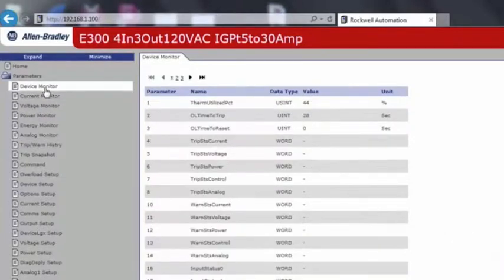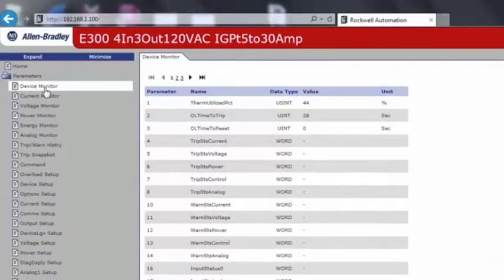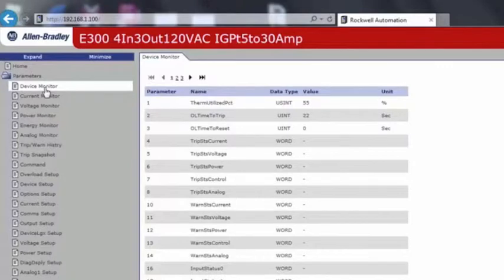On the device monitor screen, you can watch the thermal capacity usage climb, and it will trip at 100%. Below, we can see the Overload Time to Trip, which will give us a countdown.